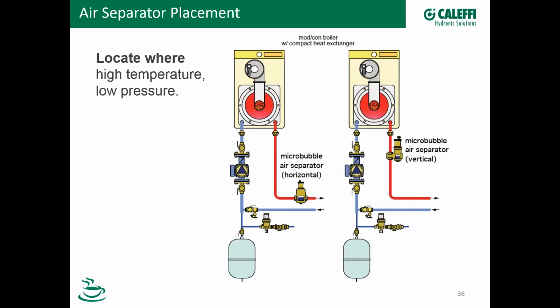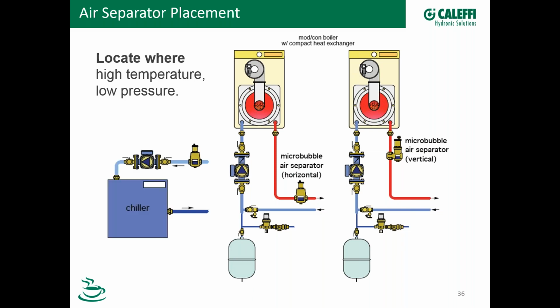Okay, let's talk about where they are placed. Because of what we talked about with pressure and temperature and removing microbubbles, we want to locate an air separator where the temperature is high and the pressure is low. So here are a couple of pictures of our schematics showing a horizontal and a vertical air separator located in the hot supply line from a ModCon boiler. And you saw this before too. On a chiller, we're going to put that in the warmest pipe, which is leading back to the chiller.